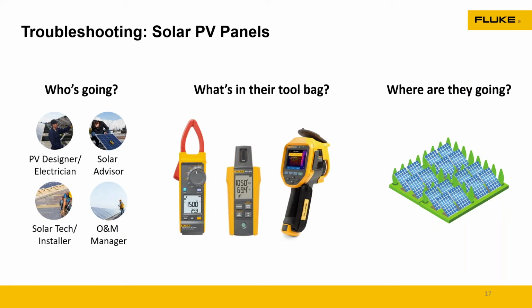Typically at this point, you're going to need a few tools. You need a clamp meter, and you need to be able to measure voltage and current. You need to know the irradiance so you can validate the output of the solar panel, so you'll need some type of irradiance meter. A thermal imager is also crucial for troubleshooting hot spots and cracks in the system.